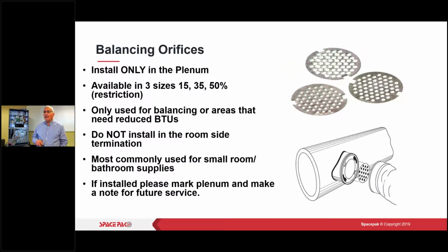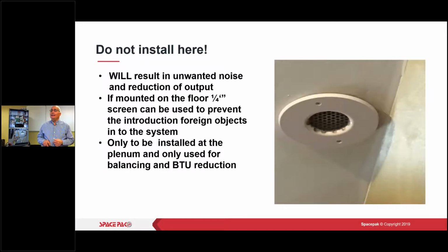Again, balancing orifices, we have them. We try not to use them. All right, they do have a tendency to be noisy. But if you're running it to a small room and you've got to get some conditioning in there, and even one outlet could be too big, then that's probably where you're going to use one of the balancing orifices. Since it comes with it doesn't mean you have to use them. Sometimes we've got jobs that have some issues and they put them in and they didn't even realize they didn't need to put them in, okay? And we never install them here. So when I first started getting involved with SpacePak and we had problem jobs, this is where we would see them, all right? And this is the reason why.